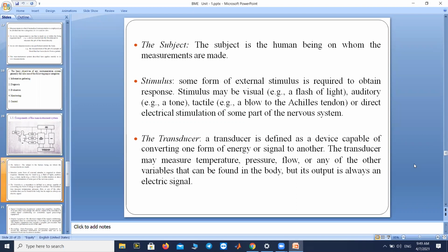Transducer is the next component. It is defined as a device capable of converting one form of energy or signal to another. The transducer may measure temperature, pressure, flow, or any other variable found in the body, but its output is always an electrical signal. You must realize that the output of a transducer is always an electrical signal.